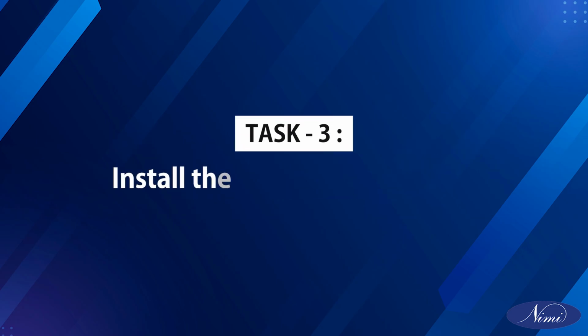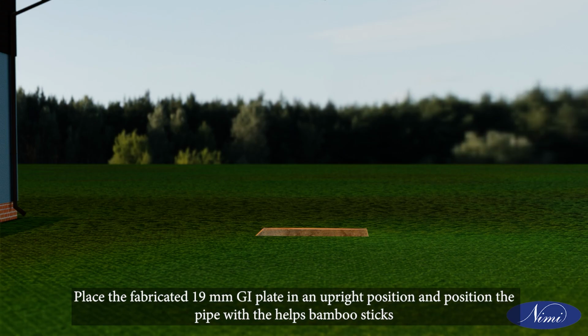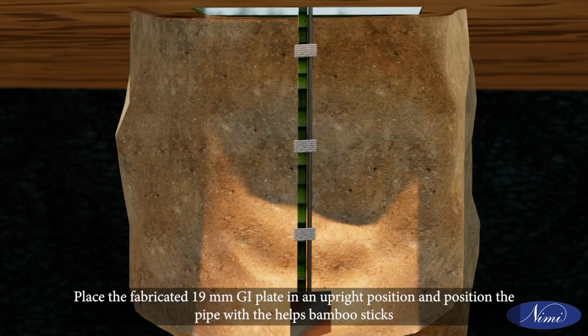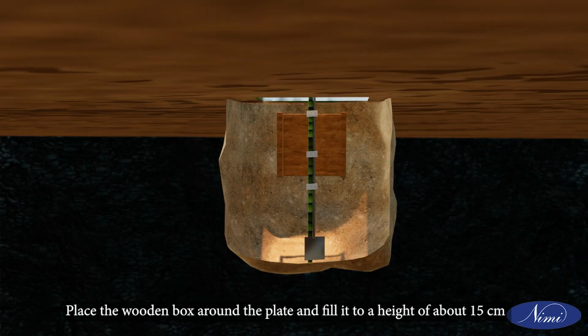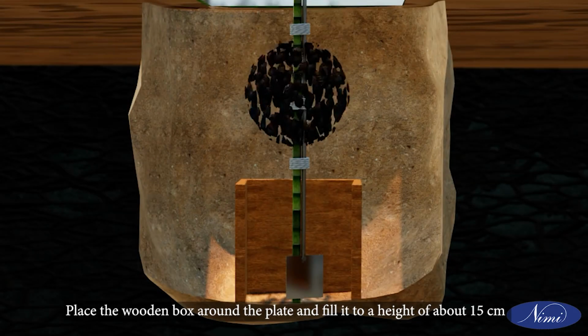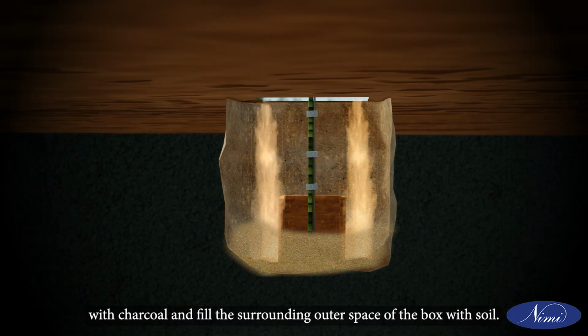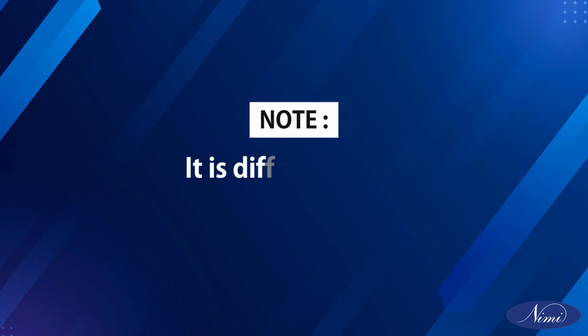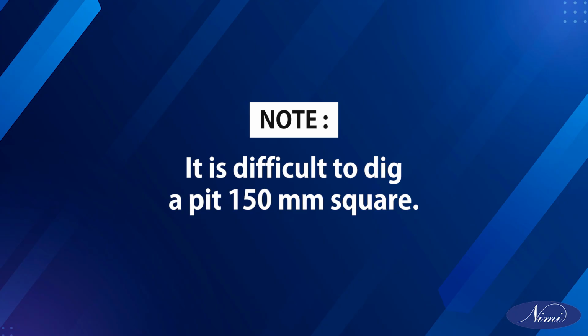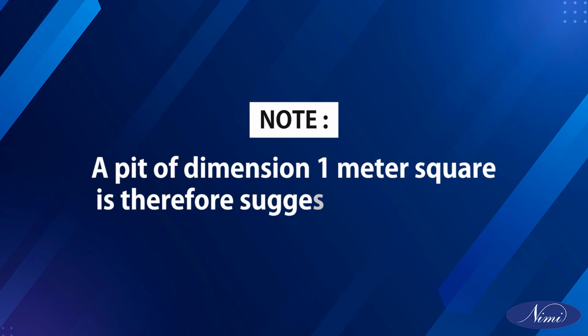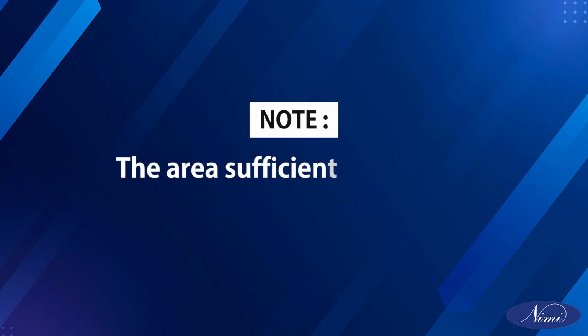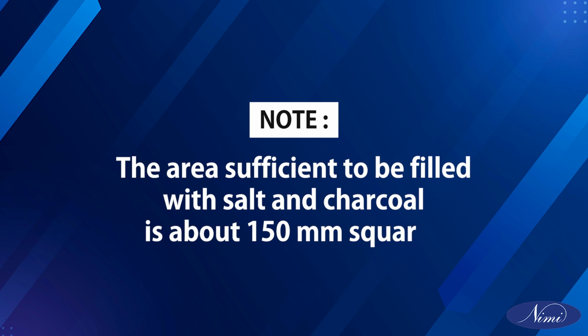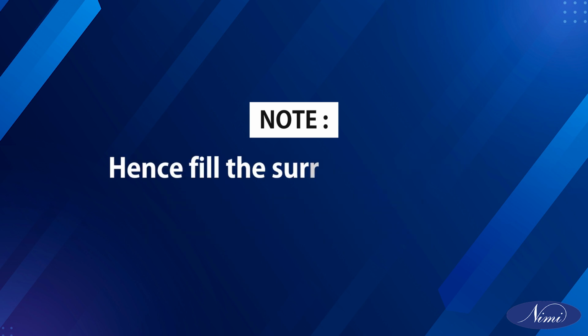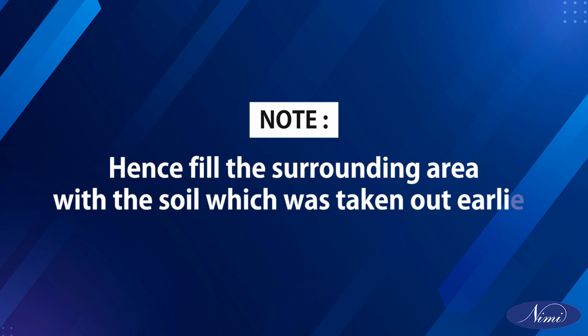Task 3. Install the plate in earthing pit already prepared. Place the fabricated GI plate in an upright position and position the pipe with the help of bamboo sticks. Place the wooden box around the plate and fill it to a height of about 15 cm with charcoal and fill the surrounding outer space of the box with soil. Note: it is difficult to dig a pit 150 mm square. A pit of dimension 1 meter square is therefore suggested to be dug. The area sufficient to be filled with salt and charcoal is about 150 mm square. Hence, fill the surrounding area with the soil which was taken out earlier.